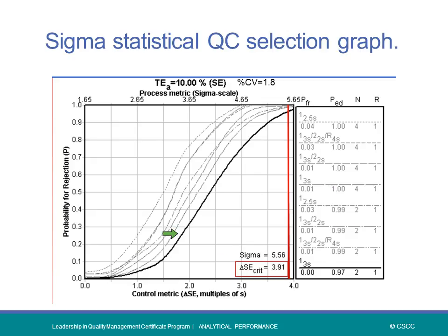And of course, we would choose those procedures that are associated with the minimal false rejection and yet maximizing error detection. And it becomes quite easy, of course, when we're dealing with a test that has a relatively high sigma and a very high critical systematic error to work with. Tests like this, however, become more of a challenge.